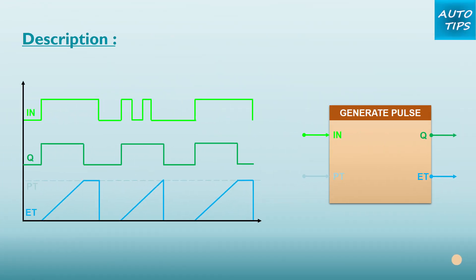You can use the Generate Pulse instruction to set the Q output for a programmed duration. The instruction is started when the result of logic operation RLO at input IN changes from 0 to 1 — a positive signal edge.